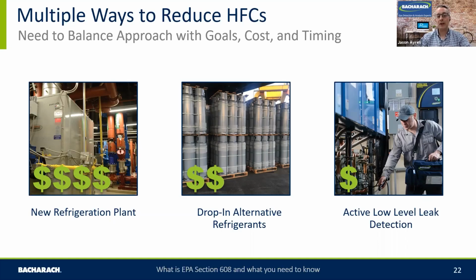But there are also other lower cost options that are available here and now. That's around leak detection. These are technologies that you can add to systems now that will help reduce and mitigate refrigerant loss, keeping that refrigerant in the system, identifying quickly and in a timely way when refrigerant is coming out so you can make repairs, and keeping costs to a minimum. If you start with that side of the spectrum, leak detection, anything you do above that is going to just reap rewards.